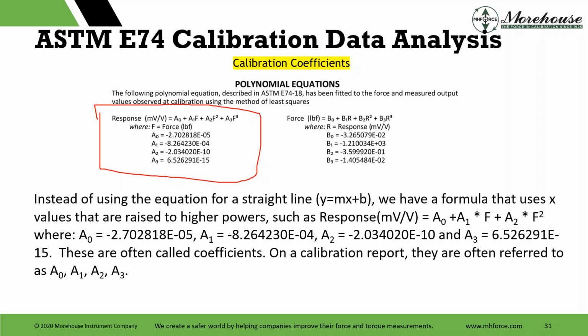So instead of using the equation for a straight line, y equals mx plus b, we have a formula that uses x values raised to higher powers, such as response, in millivolts per volt, equals, and here's our formula, A0 plus A1 times the force, plus A2 times force squared, and so on and so on. What we're looking at: A0 equals these coefficients, A1 equals that, A2 equals that, A3 equals this. These are often referred to as A0, A1, A2, A3.